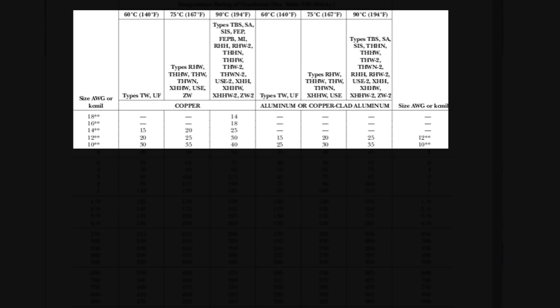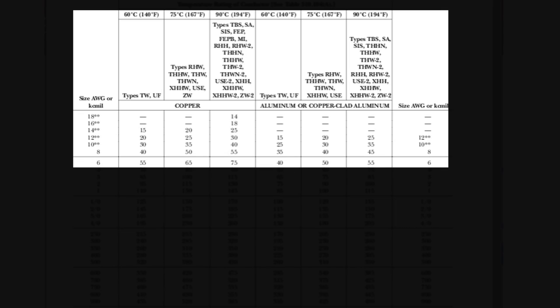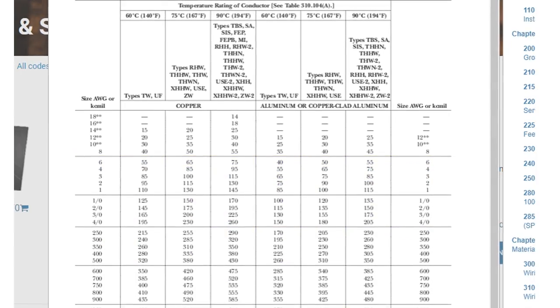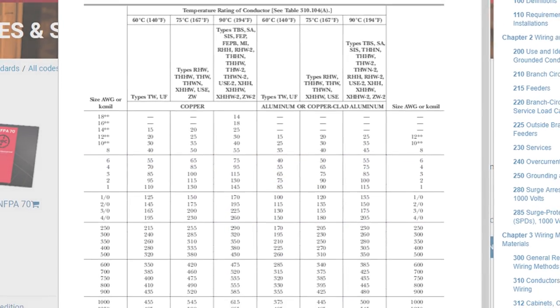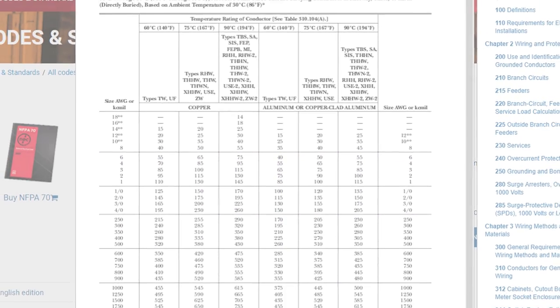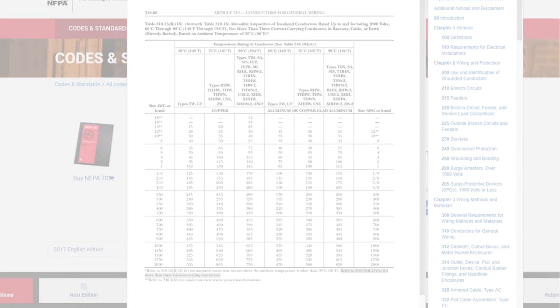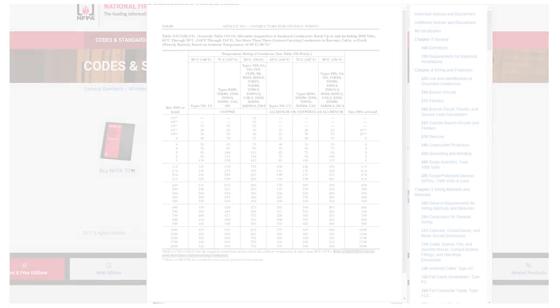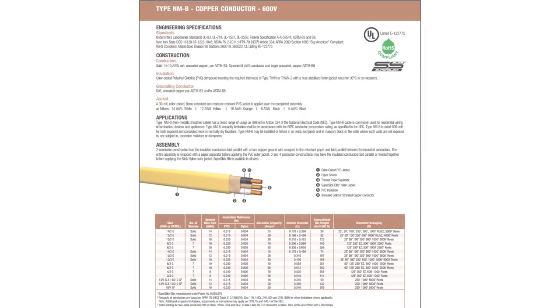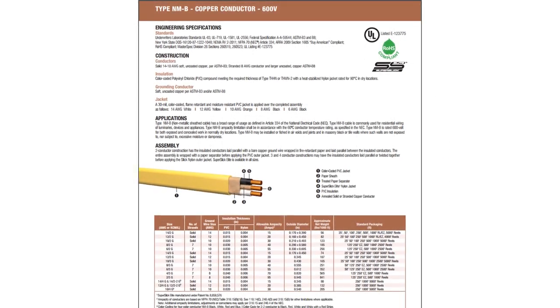That's typically what we think of, but if you look at, for example, number 6, we think 55, but number 6 is actually 65 at the 75 degrees Celsius THHN or THHW, at either 75 or 90 degrees Celsius. There are certain types of wire, certain types of assemblies that can be rated at higher amperages than what we're used to saying in our sort of rule of thumb minimums that we speak of.